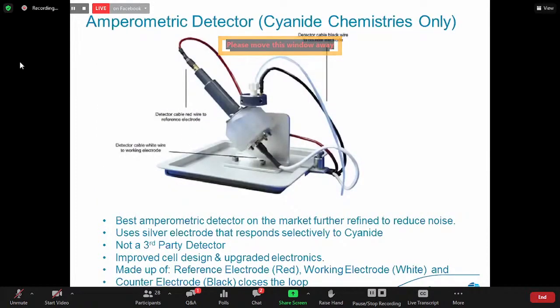As I've touched on earlier in previous slides, really at the heart of the cyanide analysis is the amperometric flow cell. And it is, in our opinion, the best amperometric detector on the market. It uses a silver electrode that responds selectively to cyanide, which is just at the bottom here. This is not a third-party detector. This is an OI design manufactured only by OI.